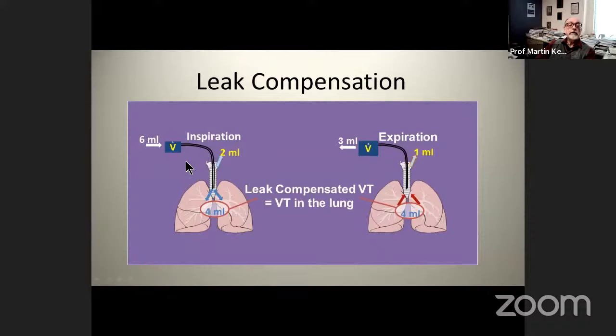But the leak is larger during inspiration. So if you have an inspiratory tidal volume measured at 6 ml, then you have a fairly large leak. 2 ml might be leaking out, and only 4 ml actually reaching the patient's lungs. But we don't measure that directly, do we? So we measure this, and we also measure the exhaled tidal volume, which in this example is 3 ml, so not as different from the volume actually in the patient's lungs as the inspiratory tidal volume. But there is some leak. So tidal volume in the lungs 4 ml, 1 ml leaks out during the expiratory phase, which is longer.